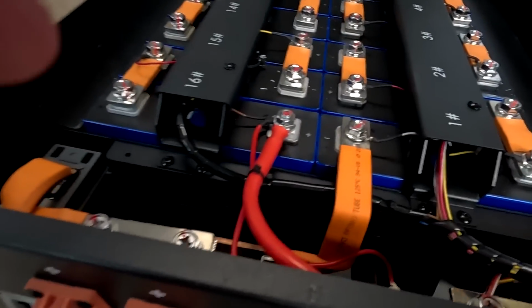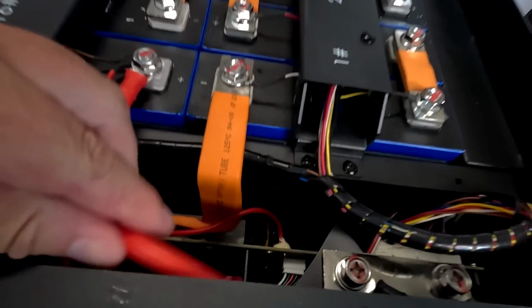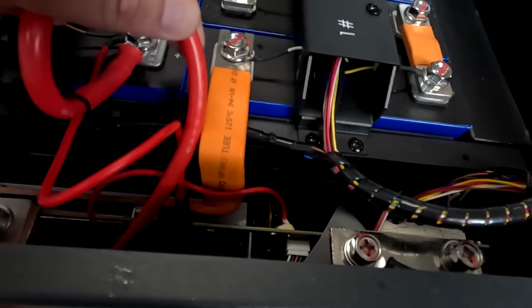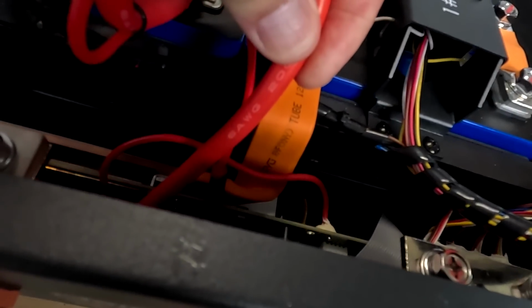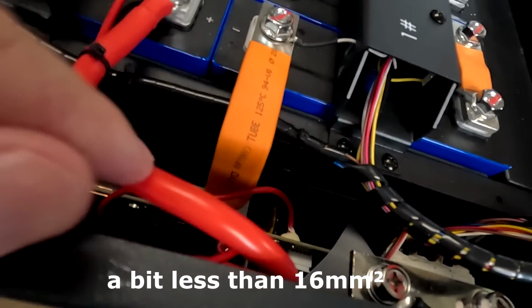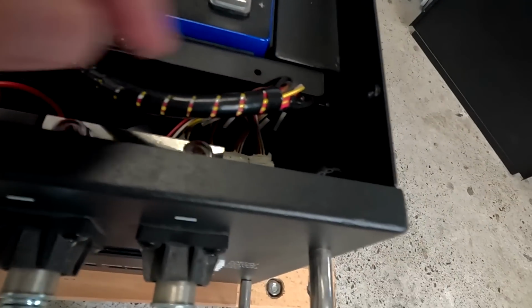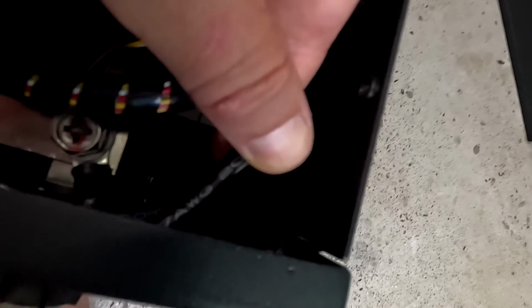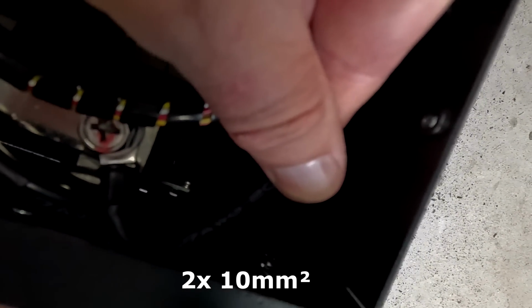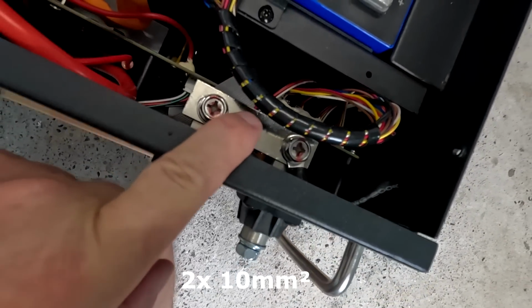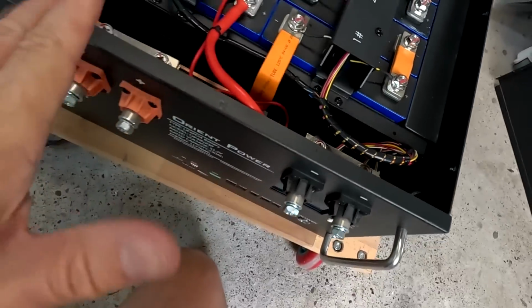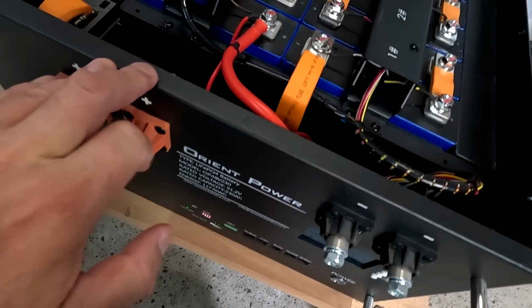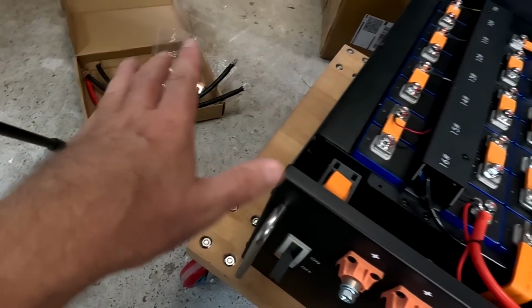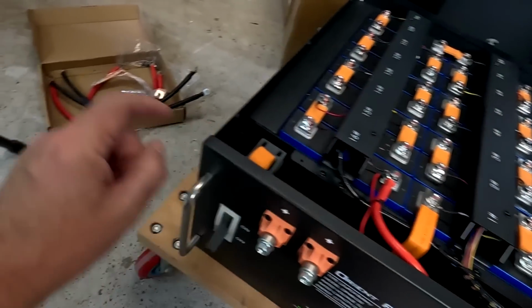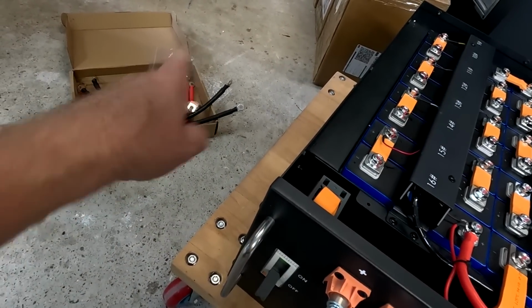See, what they did in this very first battery they ever built - they put like a 6 gauge single wire in here, and I think two 7 gauge wires for the negative coming from the BMS. I wasn't quite happy with this selection of cables for a 250 amp circuit breaker. So they actually upgraded the whole battery a long time ago with this set of cables and bus bars.